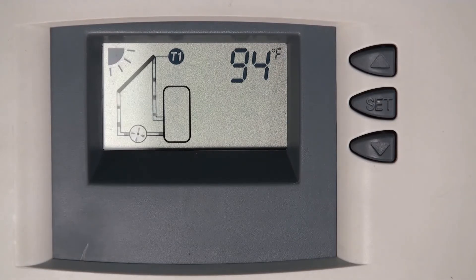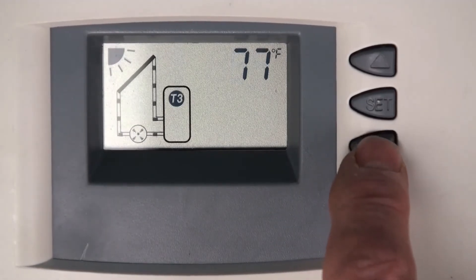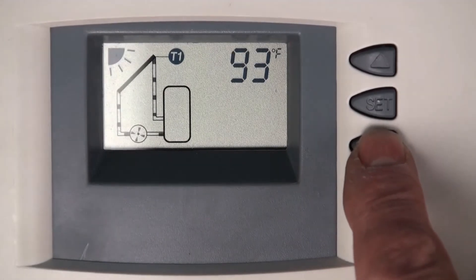So those are the first items to check. Generally on the screen you'll see temperatures like 94 degrees on the roof and then the tank at 77 or 80. I'm warming the tank up now — I just had it iced. If you put your hand over the sensor, you can see how fast these sensors react. This is just my hand gripping the sensor I spoke of in the previous video.